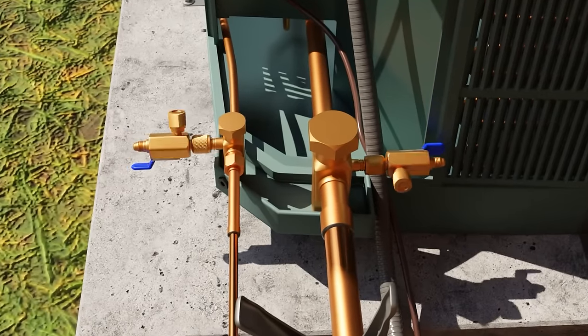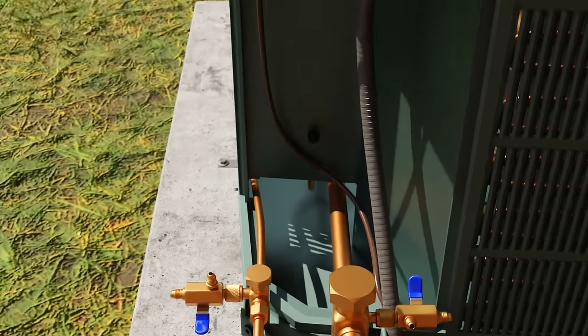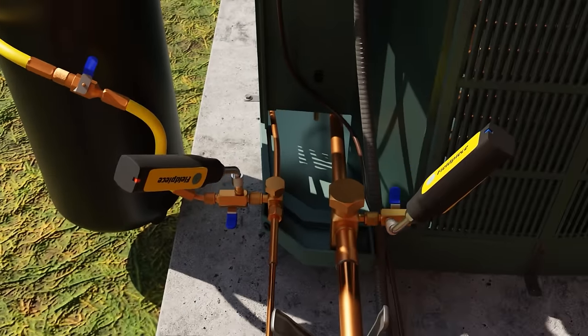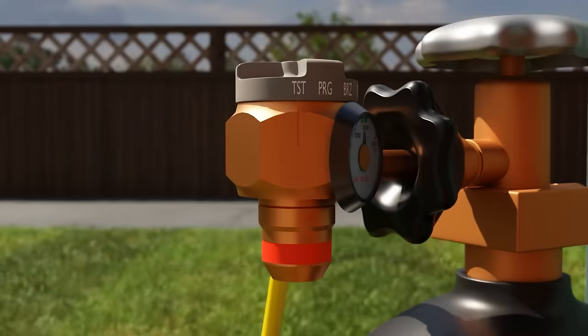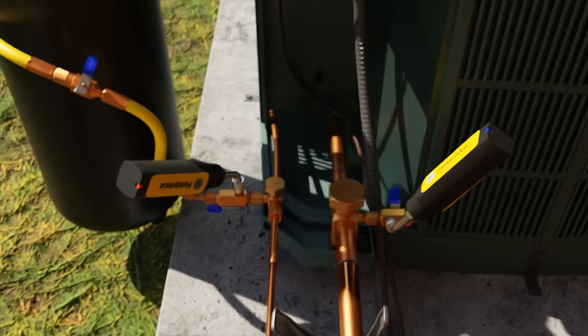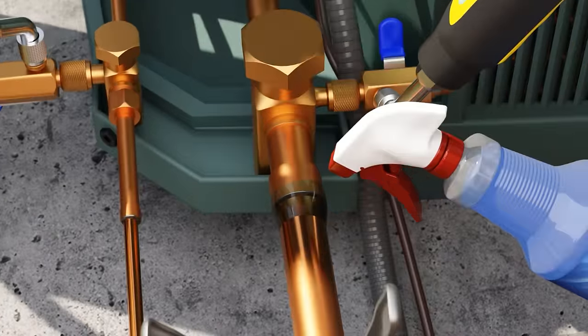Inspect all of your connections with a mirror both before and after pressurization and bubble testing. Now we're going to put core remover tools on the system and prepare for our pressure test and later our vacuum. Pressurize the system to the allowable maximum test pressure of the evaporator or condenser, whichever one is lower. Bubble test all of your connections and check with a mirror.